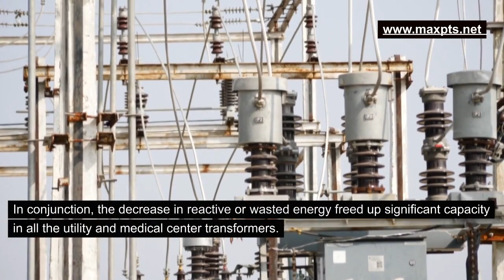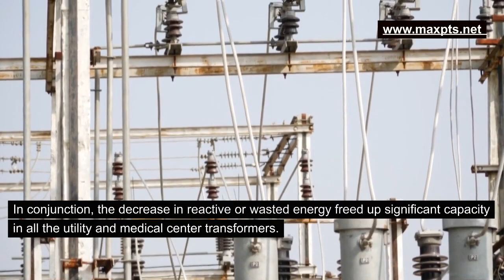What? How? Who? When? Where and why? The higher the demand side total power factor, the lower the required utility generation, utility transmission and utility distribution, and ultimately, the lower energy supply required by the medical center. In conjunction, the decrease in reactive or wasted energy freed up significant capacity in all the utility and medical center transformers. This simple theory was easily and uniquely provable with MPTS.